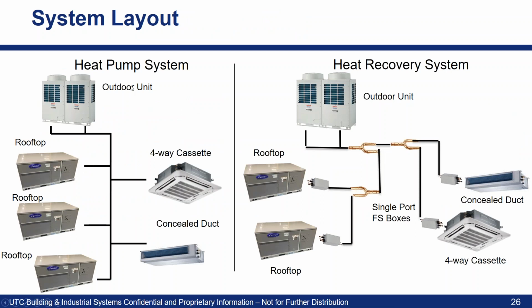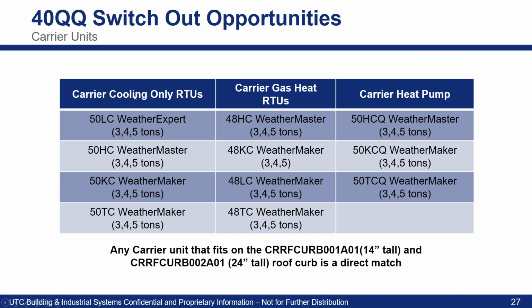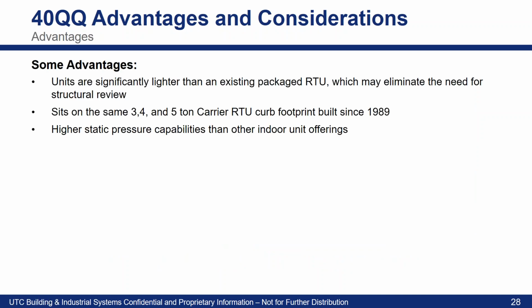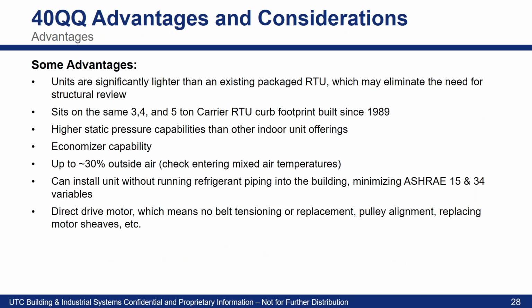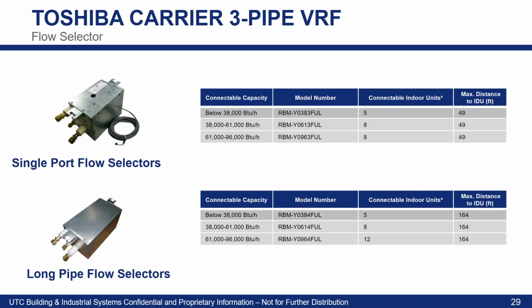Nice side-by-side comparison here, the heat pump system versus a heat recovery system. Once again, the telltale that it's a heat recovery: we have these flow selector boxes in between the outdoor unit and the fan coils. This further shows how our 40 QQ unit, which is the rooftop unit, and what footprints it will fit. Really don't need to go through the advantages there, guys. I really don't think we're going to be seeing this much, but it is available. Try to keep that in the back of your mind. So starting with our flow selectors, single port and long pipe flow selectors. Oops, sorry about that, guys.